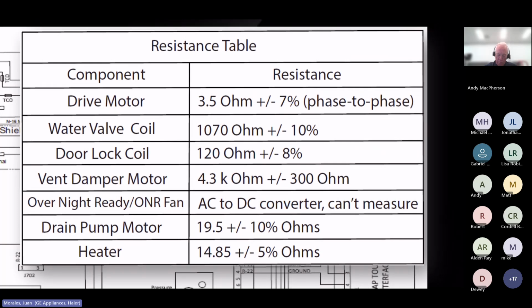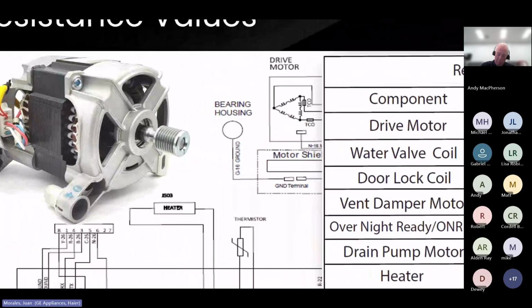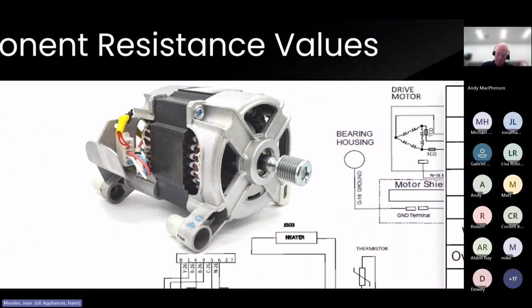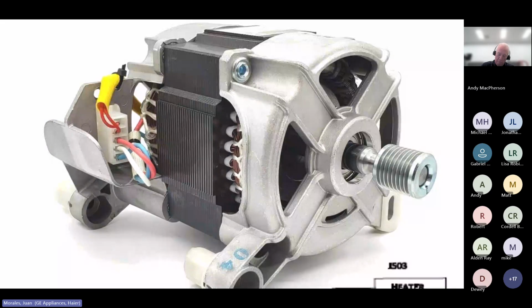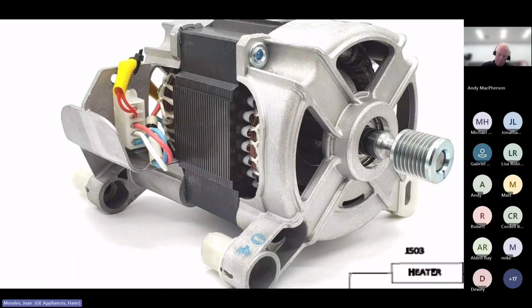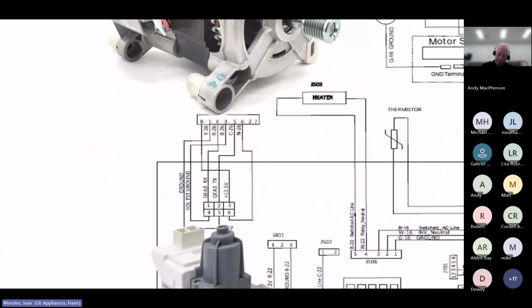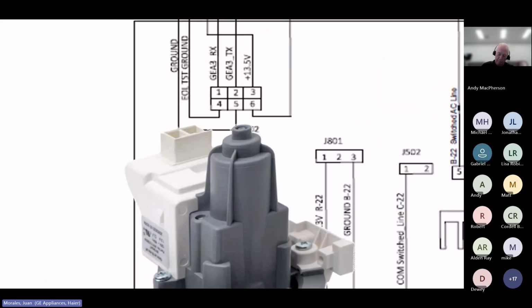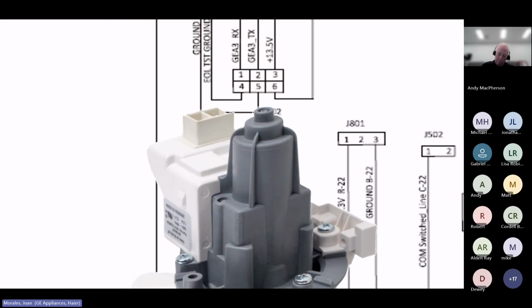Each one is going to be different. So again, if we go to the top, if you just had a bare motor sitting on your workbench and placed your multimeter leads between those red, white, and blue wires, you would get about 3.5 ohms, plus or minus 7%, something like that. If we go to the drain pump and place your multimeter leads across those two, the little holes up at the top, you would get your 19 ohms.